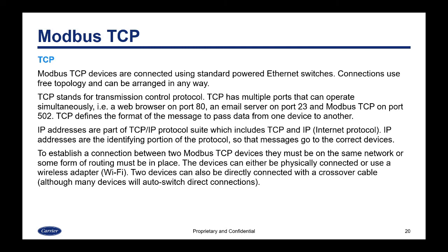TCP defines the format of the message to pass data from one device to another. IP addresses are part of the TCP/IP protocol suite, which includes TCP and IP (the Internet Protocol). IP addresses are the identifying portion of the protocol so that messages go to the correct device. To establish a connection between two Modbus TCP devices, they must be on the same network or some form of routing is in place. The devices can either be physically connected, use a wireless adapter, or connect via Wi-Fi. Two devices can also be directly connected with a crossover cable, although many devices will auto-switch direct connections.